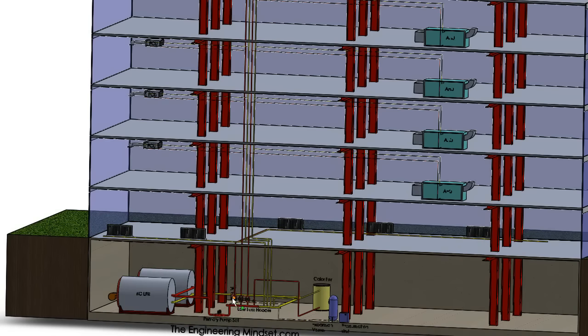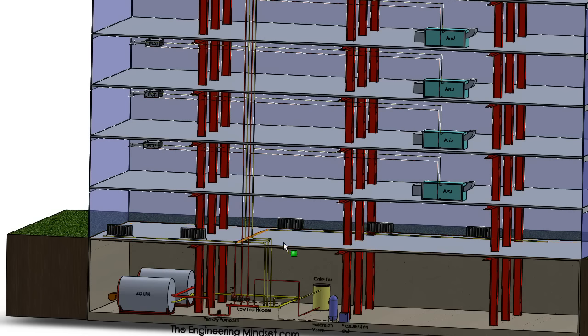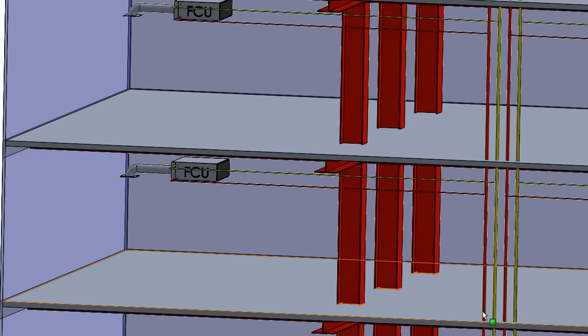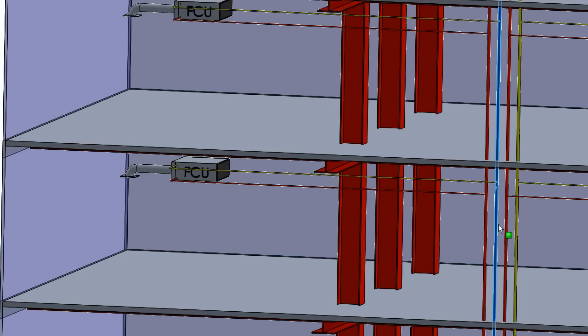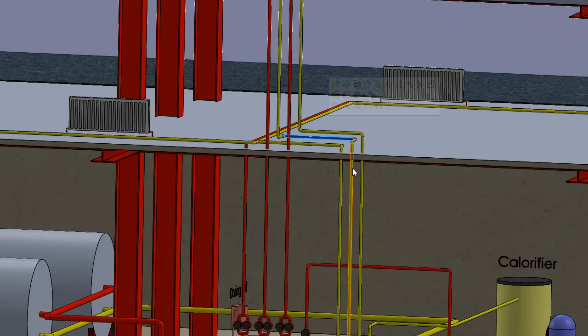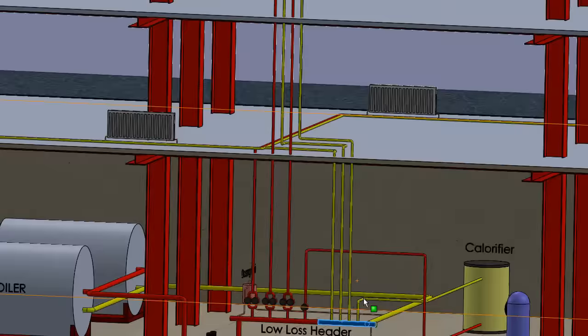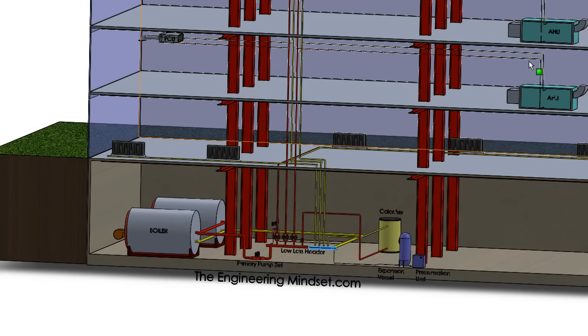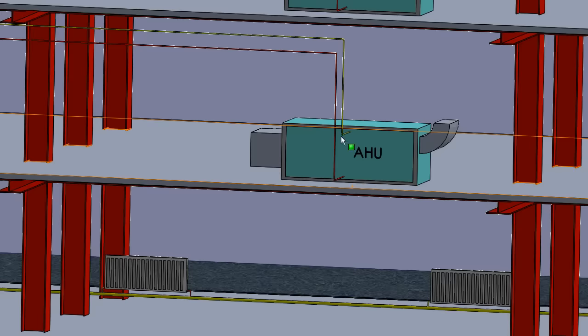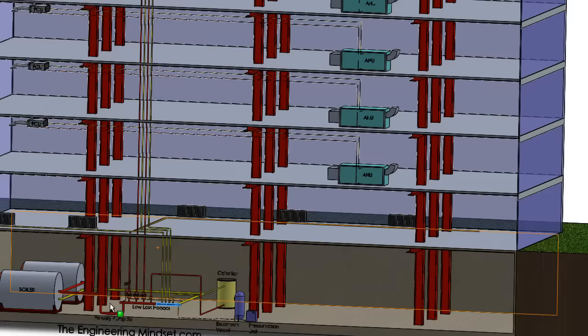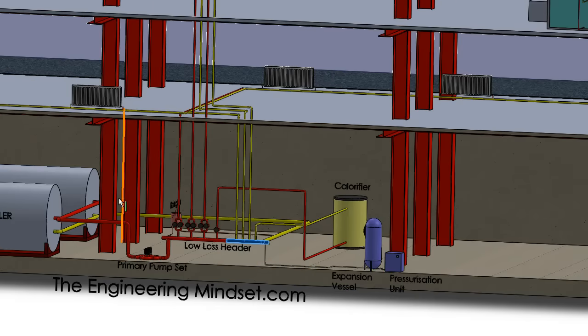You can see in this first loop it's going off and feeding some radiators on the ground floor, and that water is then returning down to the other side of the low loss header. The second secondary circuit — you can see that riser rising up the height of the building — is supplying the hot water to all of the fan coil units up here. The return is also coming back into a riser and returning back to that common low loss header. So here we've got the riser coming up, the connection coming off and feeding into that fan coil unit — the FCU. That then gives up its heat, and that water then returns cooler back to the return riser, where it makes its way through the floor and back into the low loss header. The third secondary circuit feeds up and goes off into the AHUs connected over here. That water, once it's cooler, returns back to the header and makes its way back to the low loss header, then back to the boiler to pick up more heat.